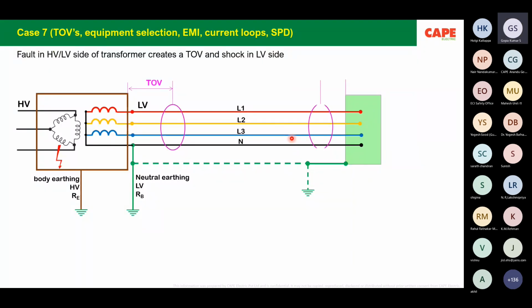The next part included, with detailed information, is about temporary overvoltages in an installation. One of the classic examples is in the newspaper. Sometimes I read that a transformer failed as a result, or the surge arrestor in the transformer is broken or failed. At the same time, several houses connected to this transformer have had electrical apparatus fail, and in some houses there are fire accidents. These are due to a phenomenon called temporary overvoltage.